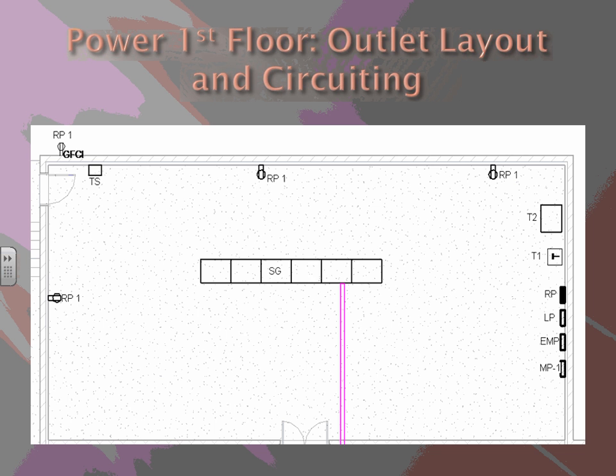This is our generator room, with the auto transfer switch up here. Basic receptacles: we only did 6 receptacles to a circuit, just kept it to 6. Our receptacle panels, lighting panels, emergency panels, and mechanical 1 panel. Our mechanical 2 panel is going to be on the 2nd floor. I'll show you that in a little bit.